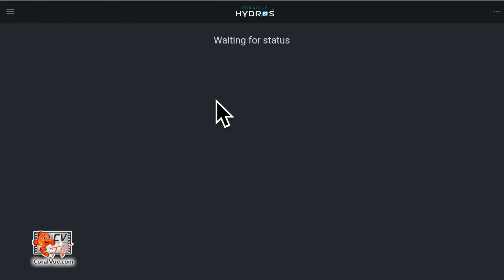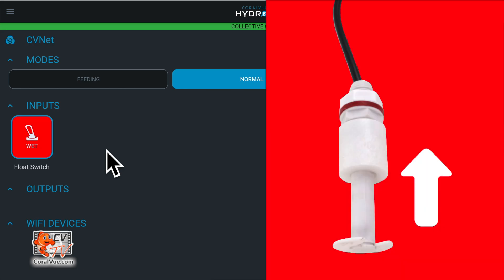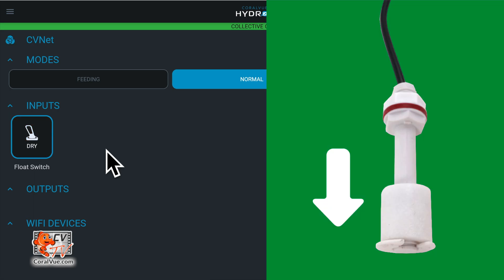Make your way back to the status screen. Now, take the float switch and manually move the magnet up. The controller should show the sensor as wet on the status screen. Lower the magnetic float and the controller should update the input and show dry.